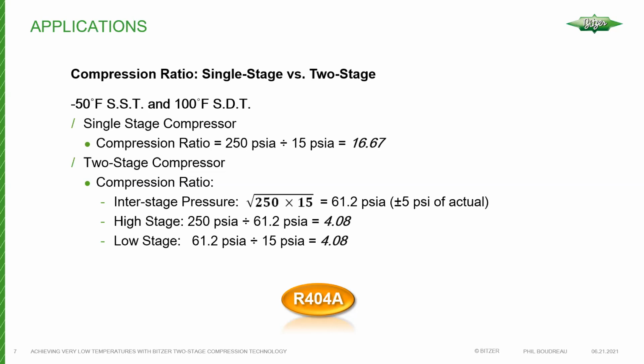Okay, so if you're working with sea level atmospheric pressure, then you would take your PSIG rating and add 14.696 or 14.7. You do that with the suction, you do that with the discharge, and you divide the suction into the discharge. So in this case, we have 250 PSIA divided by 15 PSIA, resulting in an overall compression ratio for the single stage compressor of 16.67.